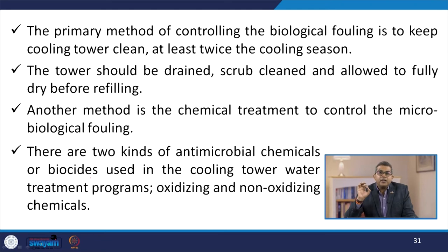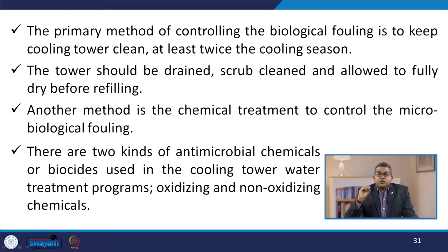The primary method of controlling biological fouling is to keep the cooling tower clean at least twice per cooling season. The tower should be drained, scrubbed, cleaned, and allowed to fully dry before refilling.